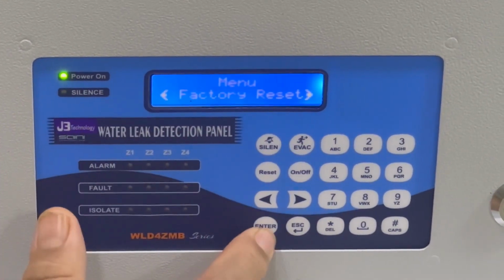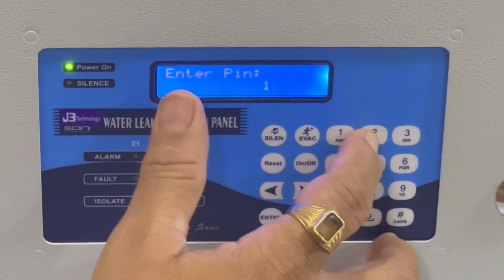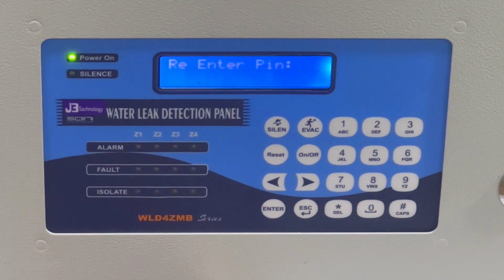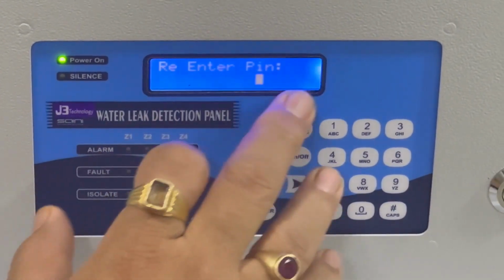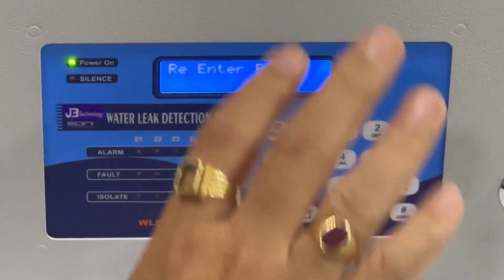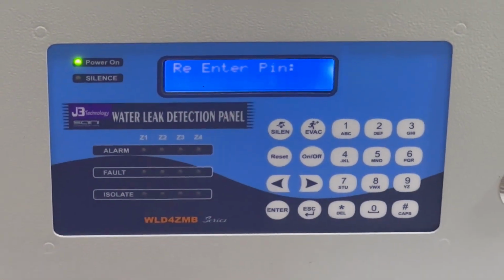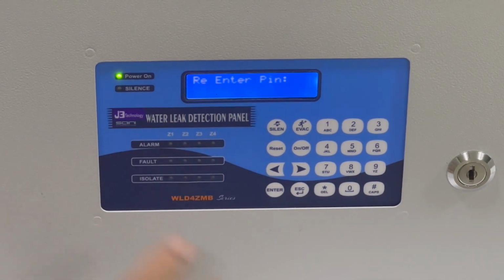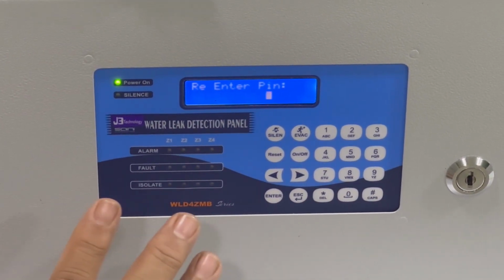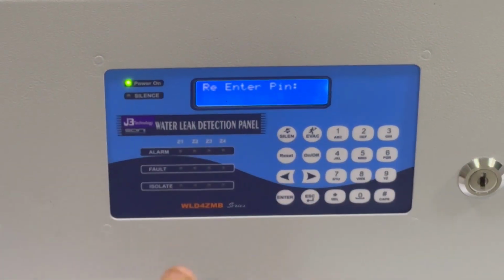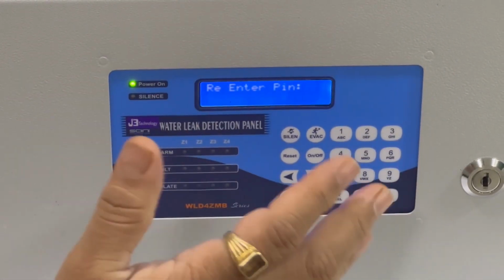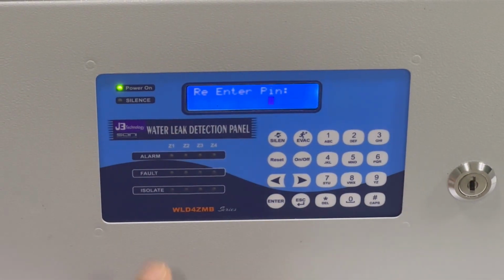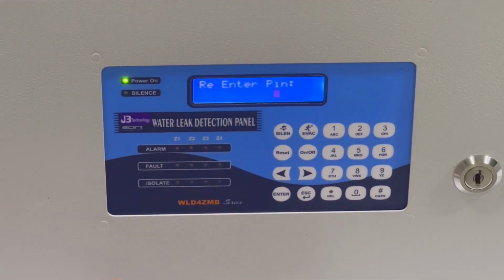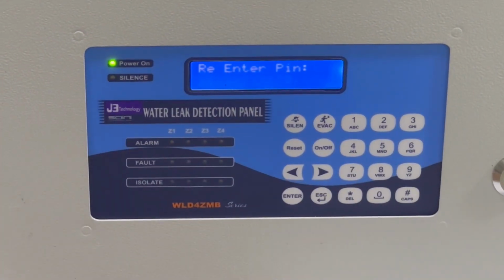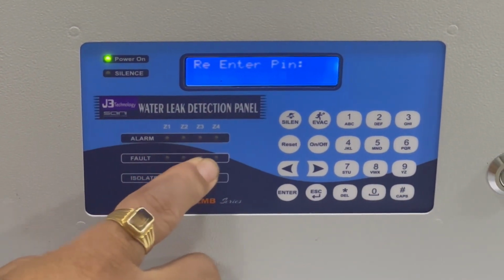For the factory reset, just enter. It will ask for the password. The factory default password is 1234. Re-enter the password, and the panel will be entirely reset. Whatever your configuration, whether zones were kept on or off, all will be changed to default mode. All zones will be activated, whether or not the sensor cable is connected. Where the sensor cable is connected, it will not show any fault. Where no sensor cable is connected, that zone will be on by default, and you will receive a fault indication on the front display, and the panel will start beeping.